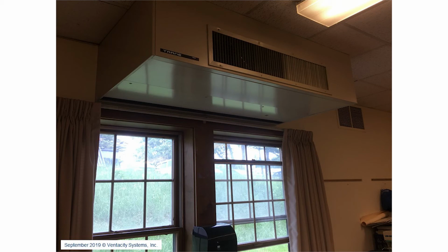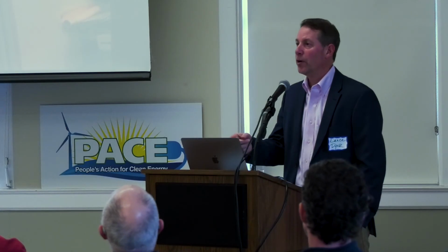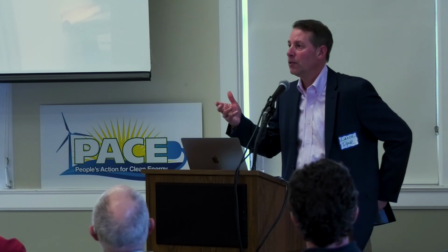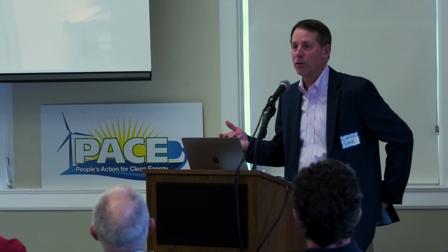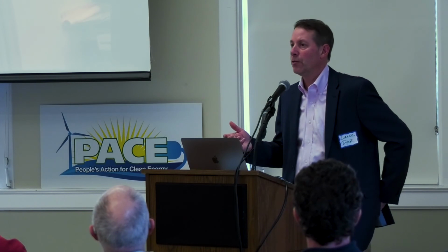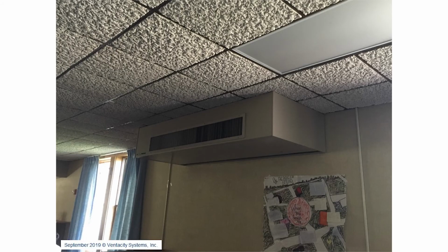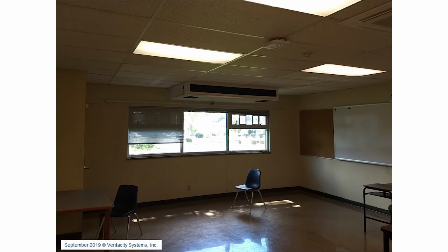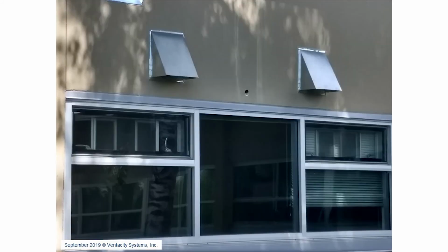And this is a job in Maine, and this is what we're replacing, a Trane unit up there that actually has a heat coil in it, and they're bringing fresh air directly from outside with a heating coil with a fossil fuel boiler in order to bring that temperature from 0 in Maine into a classroom up to something that feels comfortable to those students. A lot of energy being used in order to do that, besides the fans that are moving the air as well as the coil that's in that and the fossil fuel to do that. Kind of gives you a picture of what was there. That's what the outside looks like. One is bringing air in, one is exhausting air out.